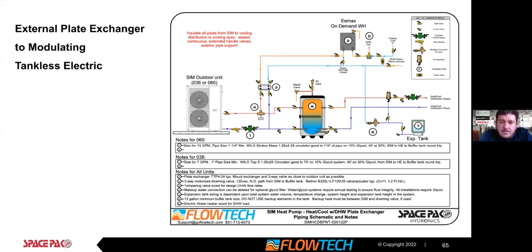This one operates very similar, where we're running into a diverting valve into a flat plate heat exchanger, but we're using a modulating electric tankless unit here. And the benefit with that is it's only going to boost what's needed. If you're sending 105, or say you're sending 110 degree water to it, it's going to take it from 110 to 120. It's not all on. So it's going to modulate down and just provide the extra energy to boost that water temperature up in line. It also avoids an extra tank. So it's a nice clean design if this is approved with local codes and energy modeling.